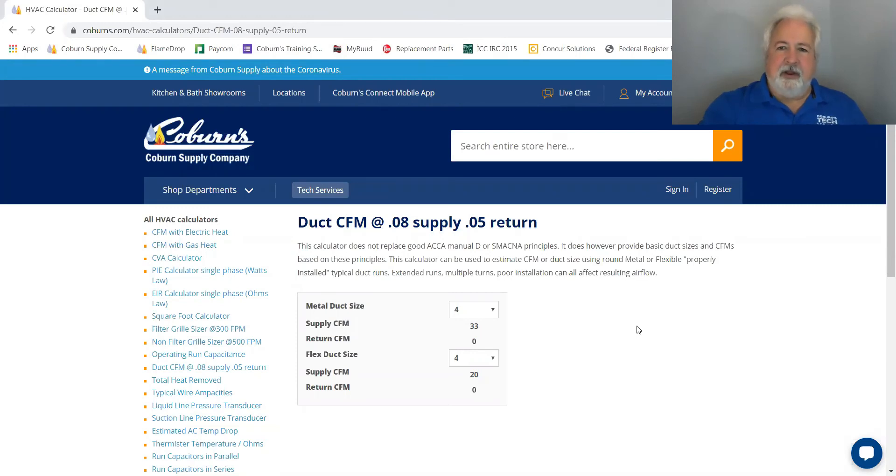The Duct CFM chart is a very useful calculator for you. Just remember that it's not to replace a Manual D, ACCA, or SMACNA's best practices. Basically what we've done is use a 0.08 supply and 0.05 return. The 0.05 return is so that we can make the return larger, slowing the air down a little bit as ACCA has recommended.